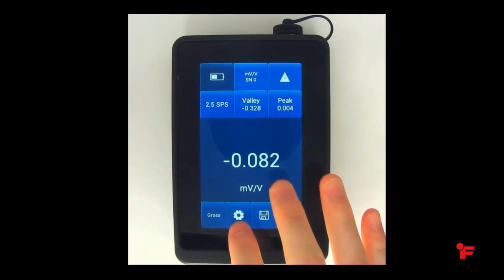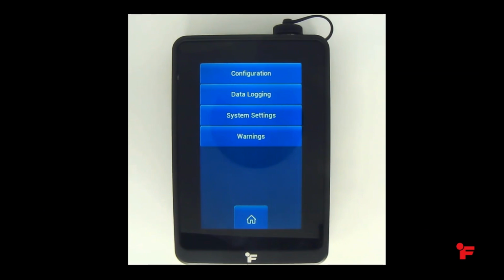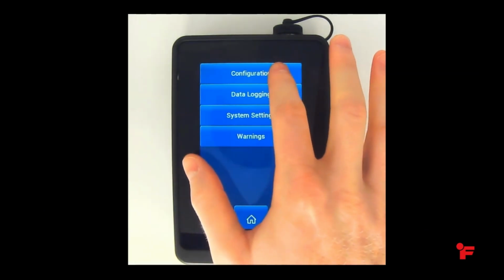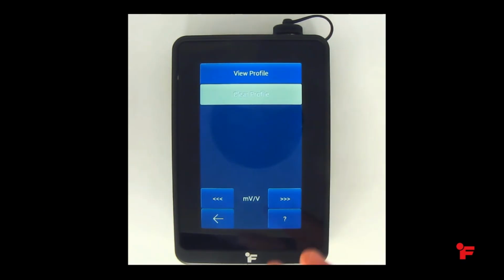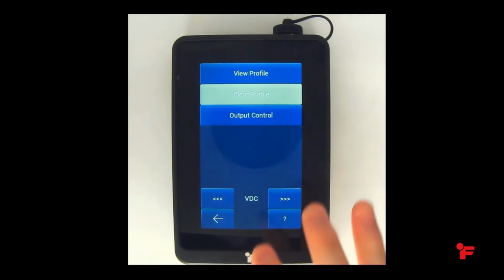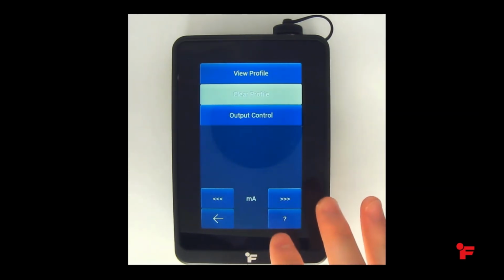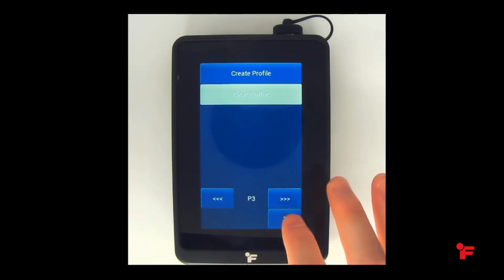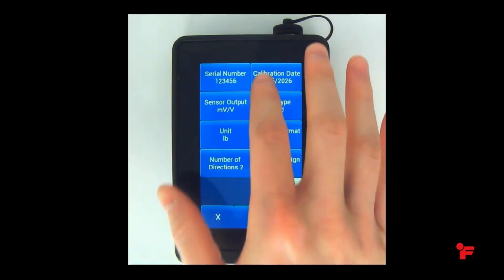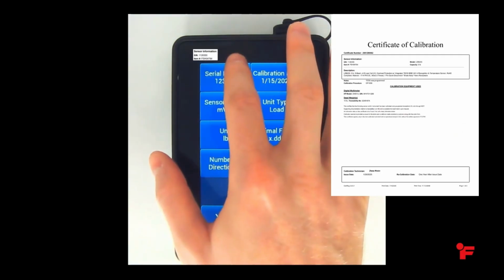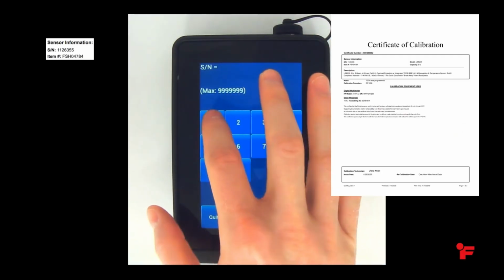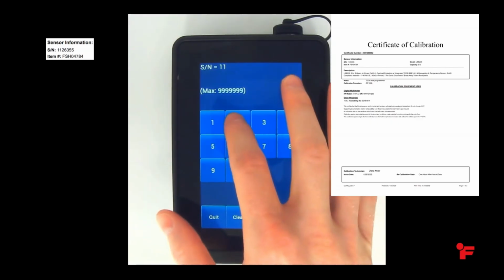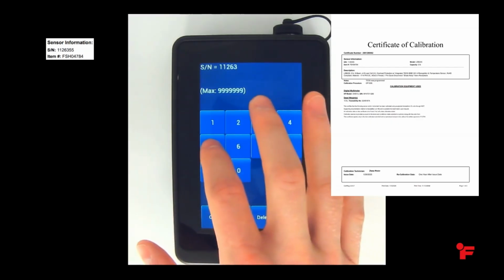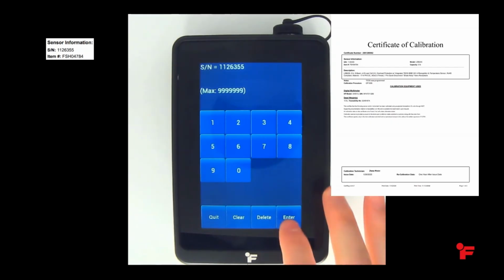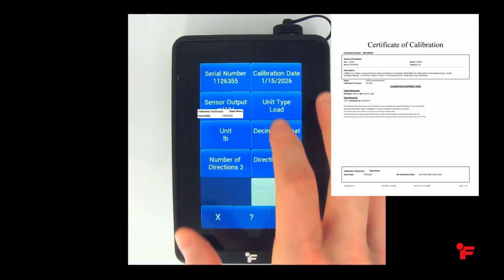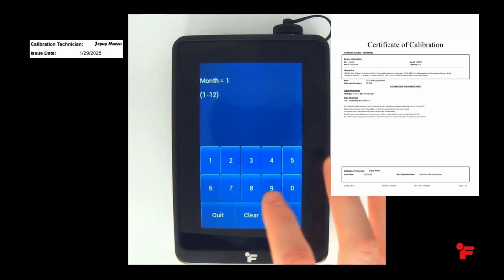To create a calibration profile, go into the menu under Configuration and use the left and right buttons to select the next available profile. The sensor serial number can be found on the calibration certificate as well as engraved on the sensor. The calibration date can also be found on the certificate of calibration.